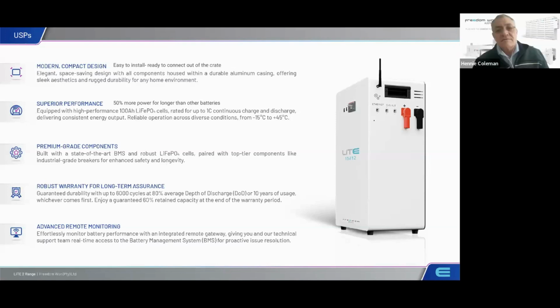From a battery safety perspective, starting with the battery management system embedded in the battery, it does soft and hard protection against electrical events like surge in current or voltage. In some cases it will soft protect the battery and switch off, but in other cases, depending on the criticality of the event, it will physically trip the breaker and disconnect the battery from the system.